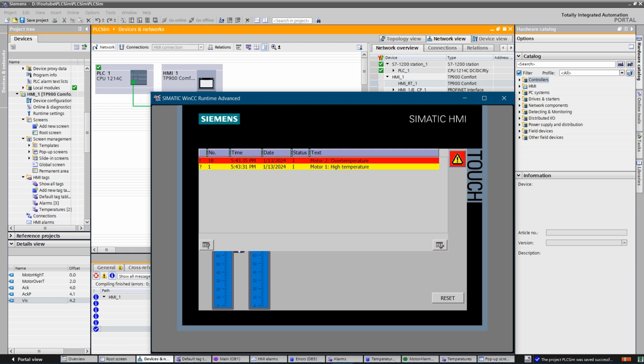An error is activated when a motor reaches a temperature of 90 degrees Celsius. On error, the operator gets a different message on actions to be taken, compared to a warning. If an error occurs, the motor will be stopped to avoid further damage to the equipment.